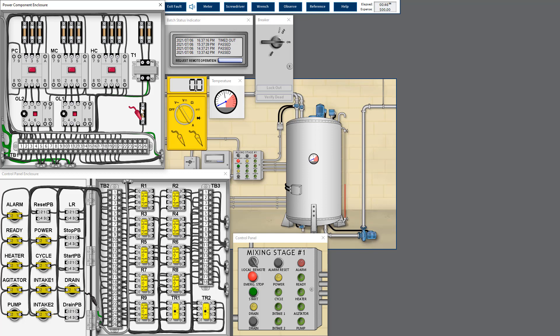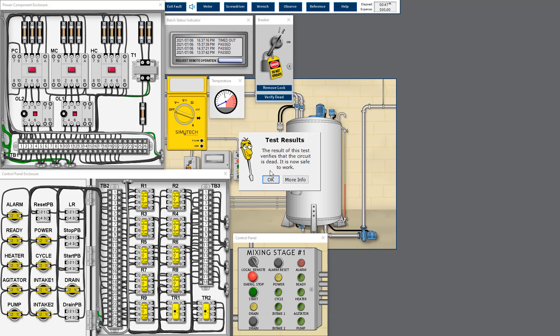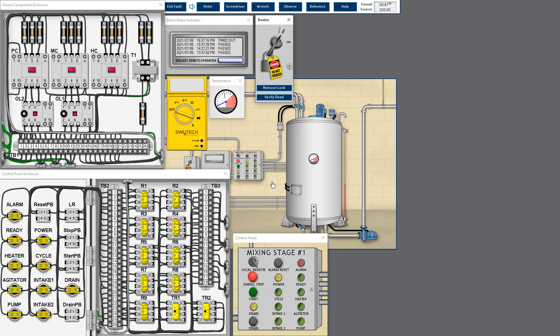The fuse blows because of a short circuit, which can be due to a fault or a device internally short circuit. No matter what, we have to check the resistance for both types of faults. As we know, resistance cannot be measured live, so we have to cut the power supply so that the circuit is dead. Switch to resistance mode on the multimeter, cut off the power supply, and perform the local lockout/tagout, verifying it is done properly.